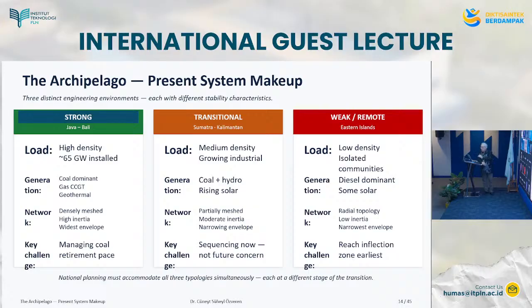Low system strength means that single unit trips are a large percentage of the total generation capacity, and of course they have a high reactance to resistance ratio on distribution cables. Reactive compensation is scarce, fault level is low, the protection system sees smaller fault currents, and voltage recovery after a fault is slower without synchronous plant. So islands are most susceptible because they have 1 or 2 diesel generators and the rest is solar plant, which has no inertia. So you lose 1 generator, and it has a huge effect on the system.